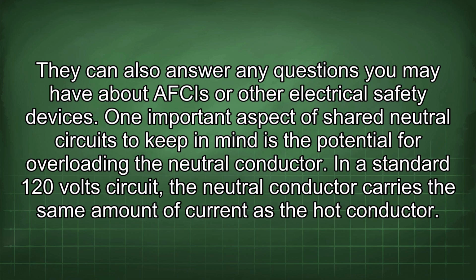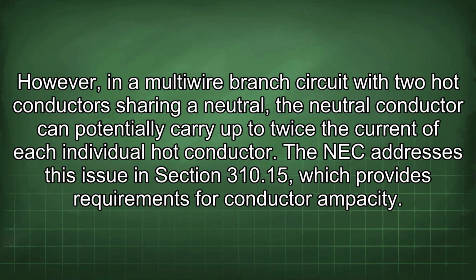One important aspect of shared neutral circuits to keep in mind is the potential for overloading the neutral conductor. In a standard 120-volt circuit, the neutral conductor carries the same amount of current as the hot conductor. However, in a multi-wire branch circuit with two hot conductors sharing a neutral, the neutral conductor can potentially carry up to twice the current of each individual hot conductor.